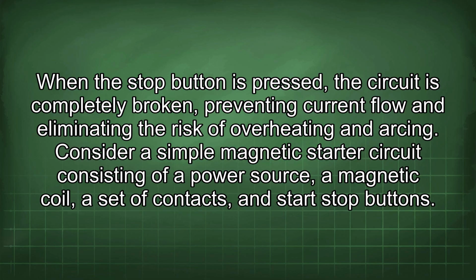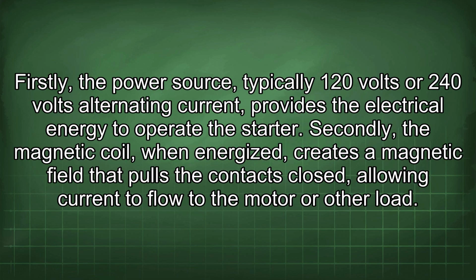Consider a simple magnetic starter circuit consisting of a power source, a magnetic coil, a set of contacts, and start-stop buttons. Firstly, the power source, typically 120 volts or 240 volts alternating current, provides the electrical energy to operate the starter. Secondly, the magnetic coil, when energized, creates a magnetic field that pulls the contacts closed, allowing current to flow to the motor or other load.